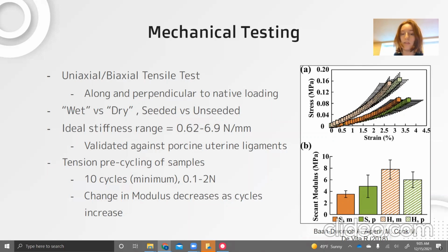And we would validate this against porcine uterine ligaments, which seem to have the same mechanical properties as the human uterosacral ligament. During these tests, we would also pre-cycle it with tension along the native loading direction with a minimum of 10 cycles ranging from 0.1 to 2 newtons. And this is because the change in modulus, the secant modulus specifically, decreases as the cycling increases. So there, at the beginning, there's a large increase and that sort of tapers off.